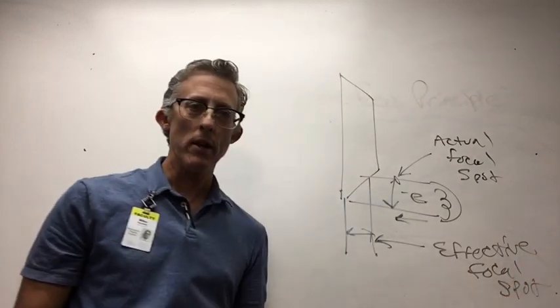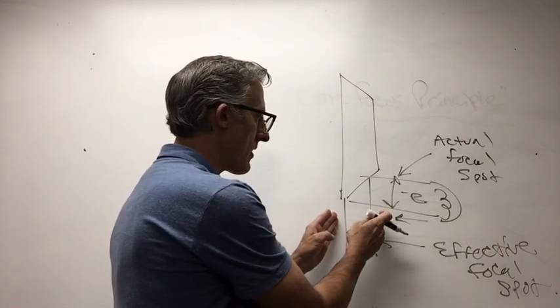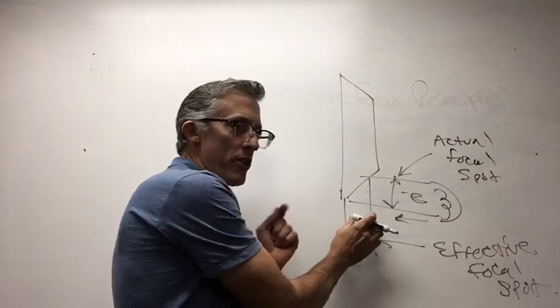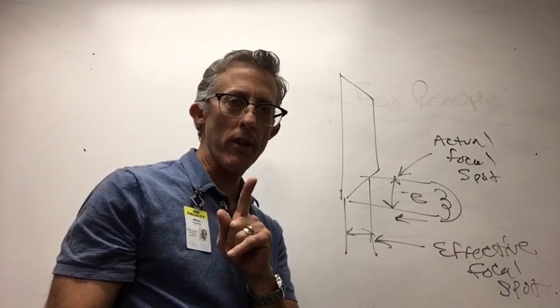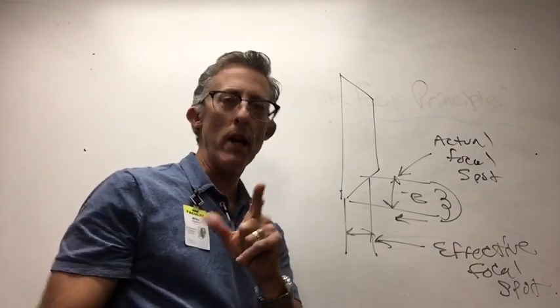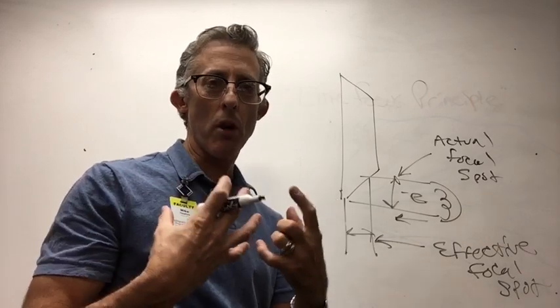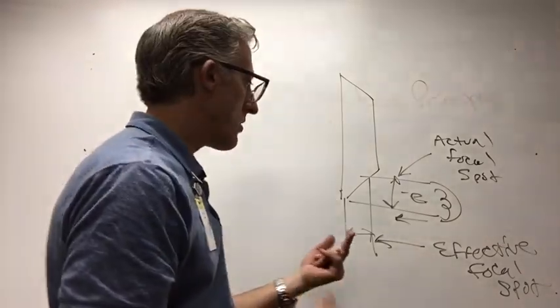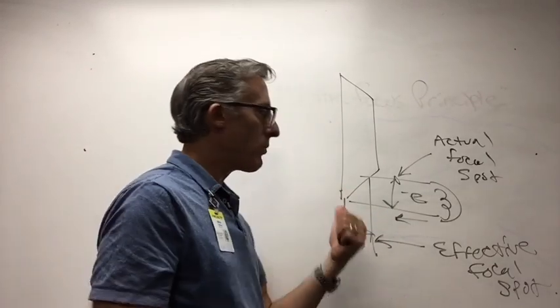Because our goal, if we were engineers and building an x-ray tube, our goal would be to make this, the width of this effective focal spot, as narrow as possible. That's going to do one very important thing, folks. That's going to improve the detail of your radiographic image. It's going to make everything sharper and easier to visualize. But this has to be narrow. So how can we do that?